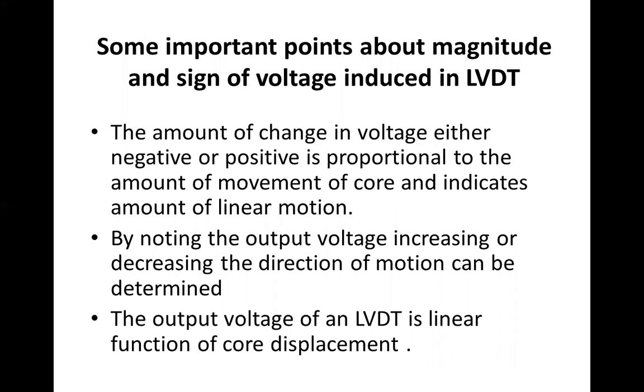Some important points about magnitude and sign of voltage induced in LVDT. The amount of change in voltage, either negative or positive, is proportional to the amount of movement of core and indicates amount of linear motion. By noting the output voltage increasing or decreasing, the direction of motion can be determined. The output voltage of an LVDT is a linear function of core displacement.